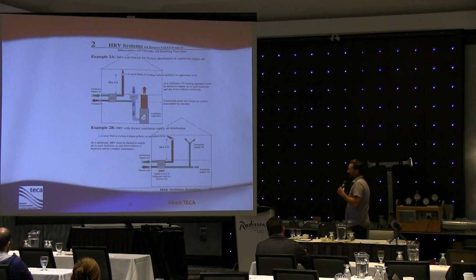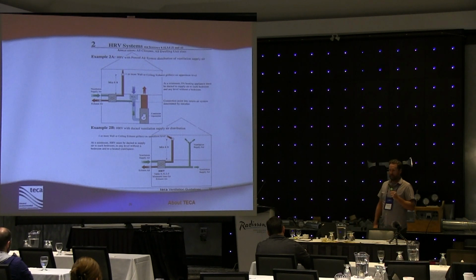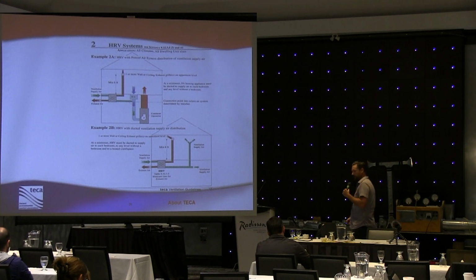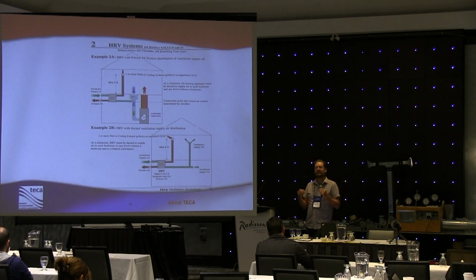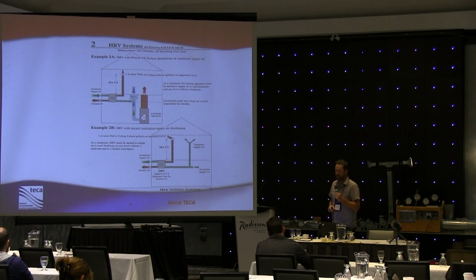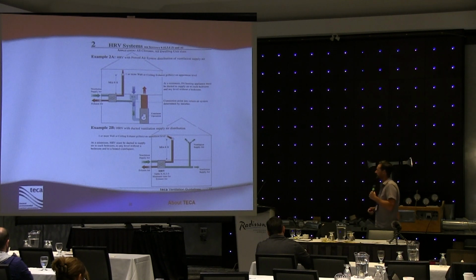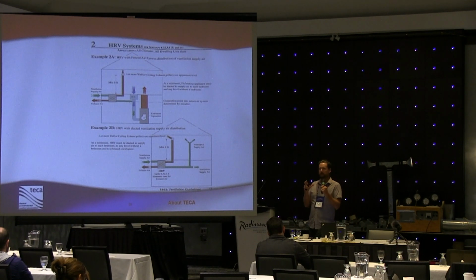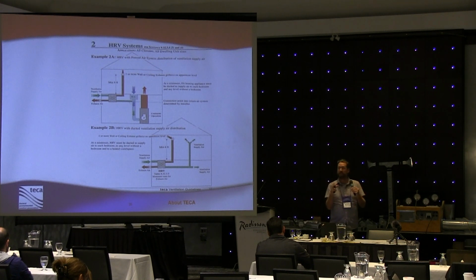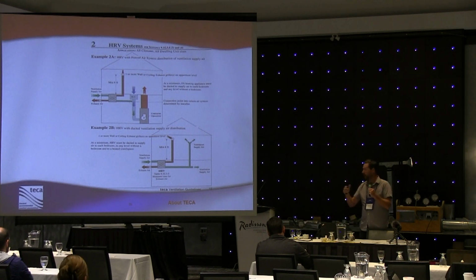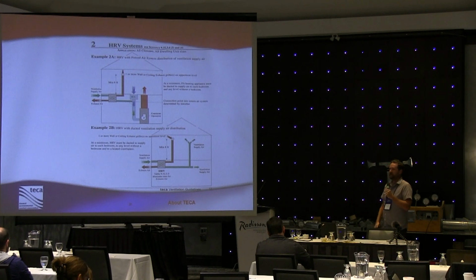The other type of unit, like an HRV, there's another unit out there called an ERV, which stands for Energy Recovery Ventilator. Well, the HRV does a really good job of stripping the heat energy directly out of the air that we're exhausting to the outside. Does a great job of that, usually somewhere between 50 and 60% effective. An ERV is slightly more effective because it has a heat exchanger that has what's called a semi-permeable membrane in it. It allows latent moisture, or water that's in its vapor form, to pass through. Some of that water can pass through the heat exchanger.